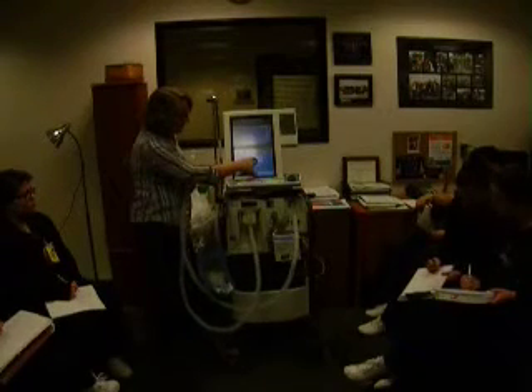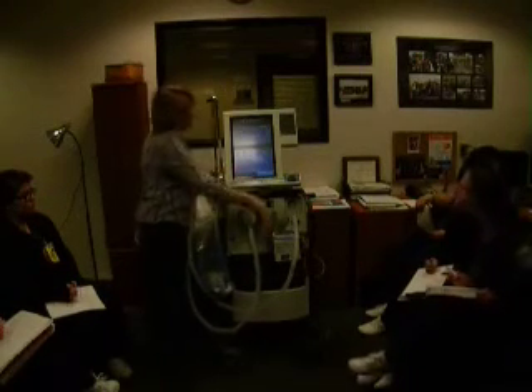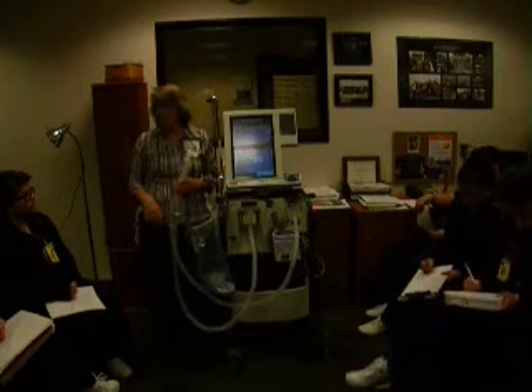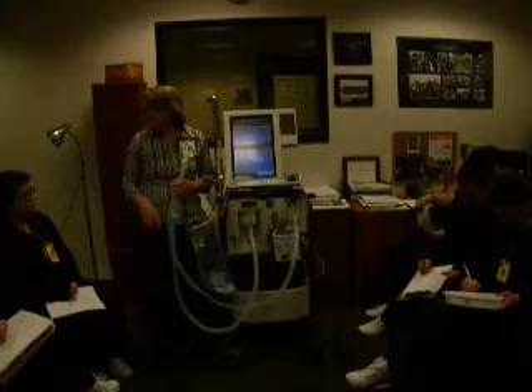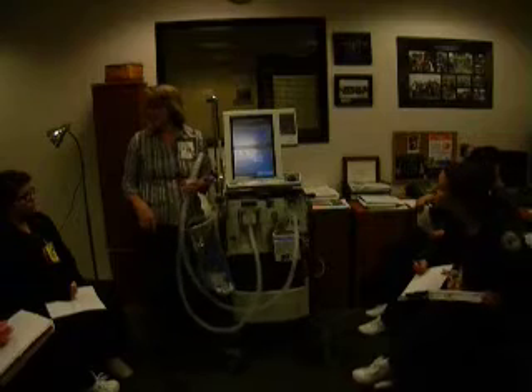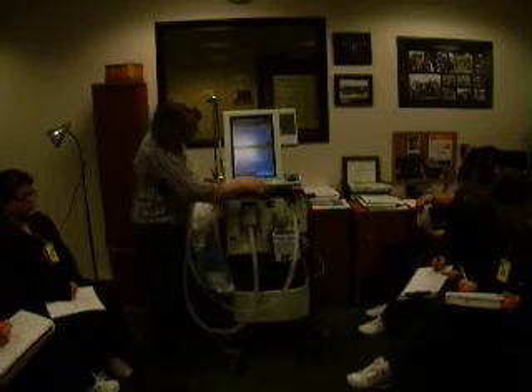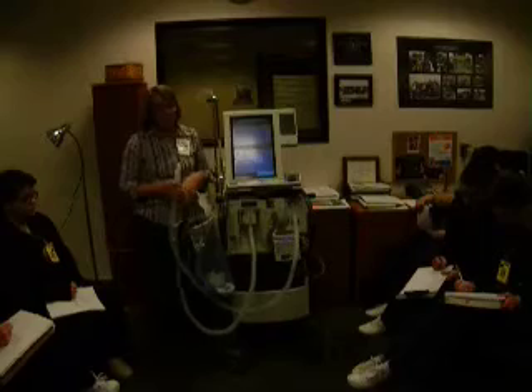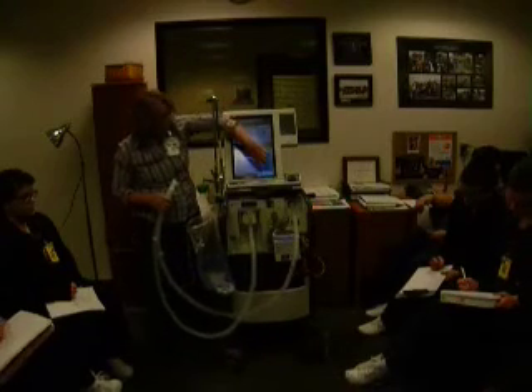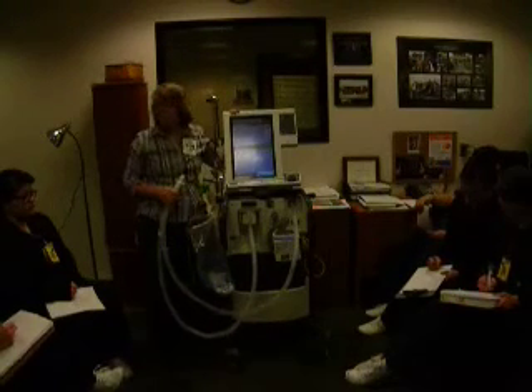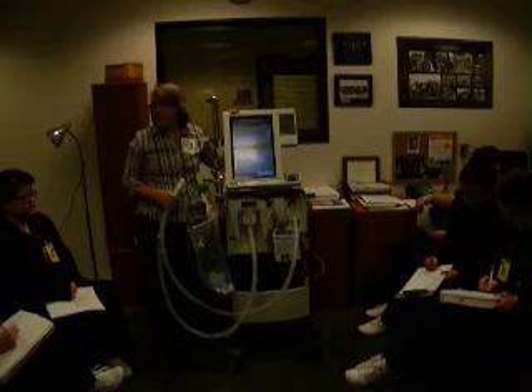And then humidifier volume, if we had the humidifier on here, it's just asking how much water it holds. Is the heated expiratory tube really heating the expiratory? It heats both sides actually. Yep. And so once you set that, you'll see at the bottom of the Puritan Bennett, there's a little screen that's either blue or orange that tells you what it wants you to do. So if you don't know what to do next, look there.